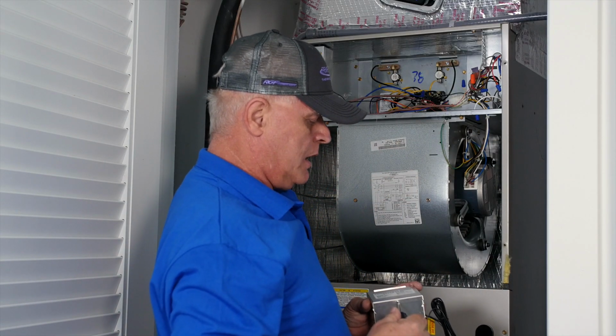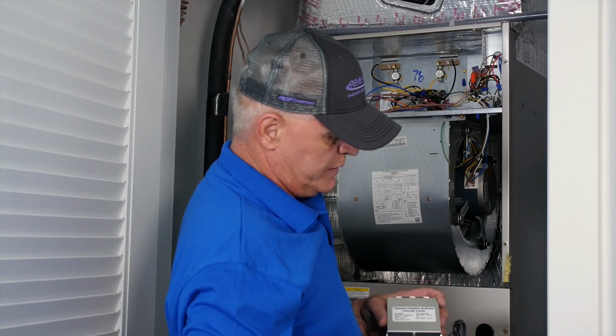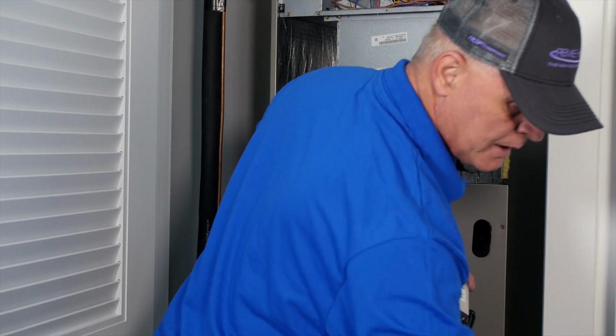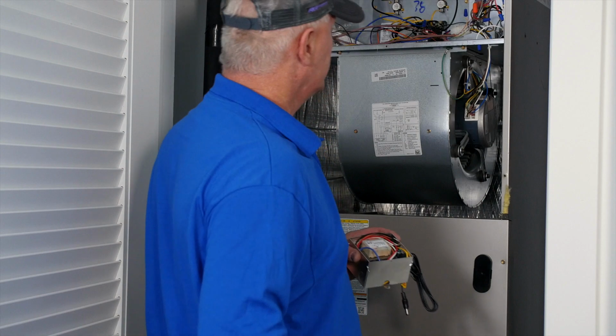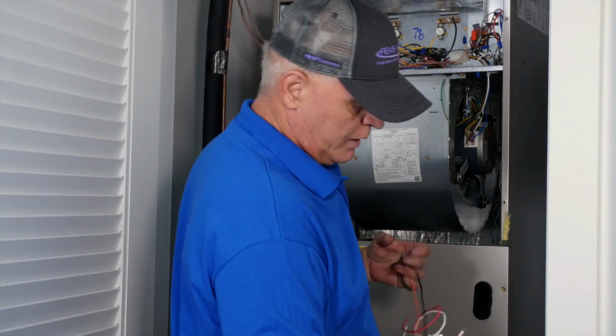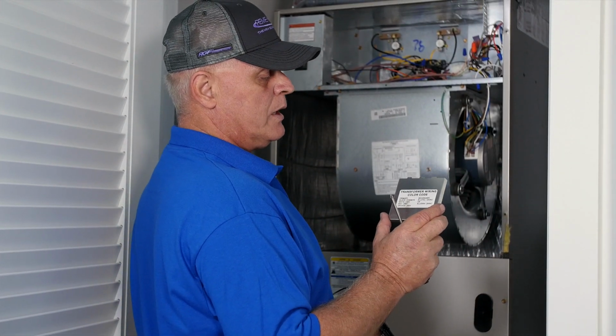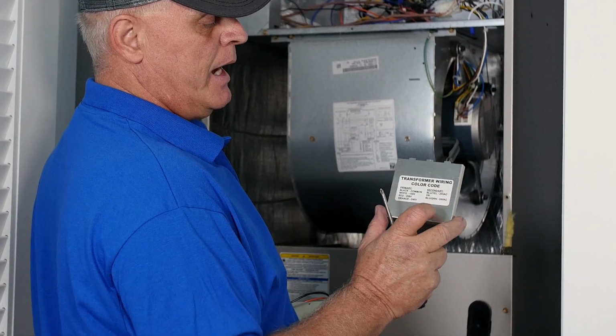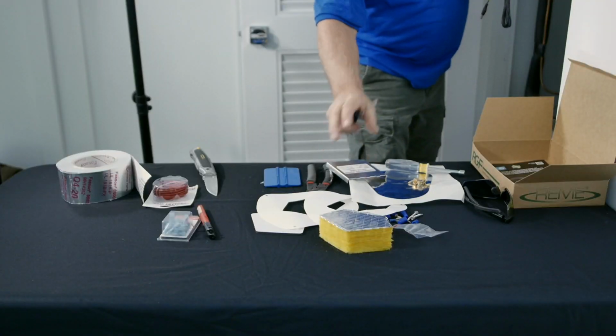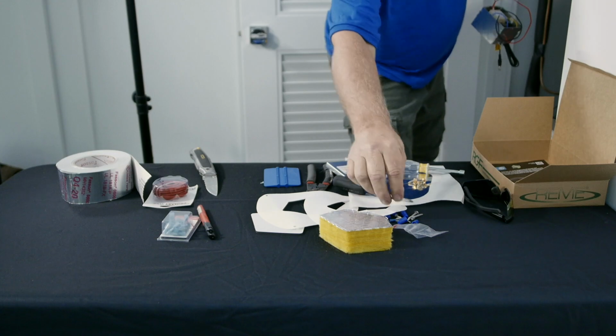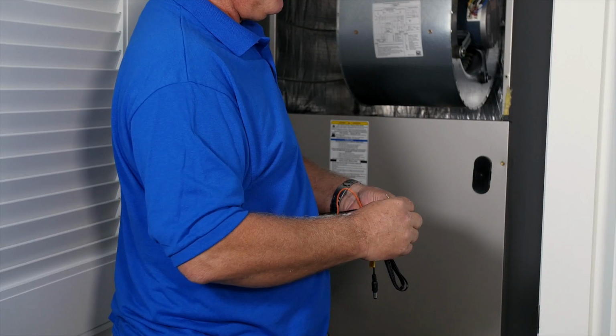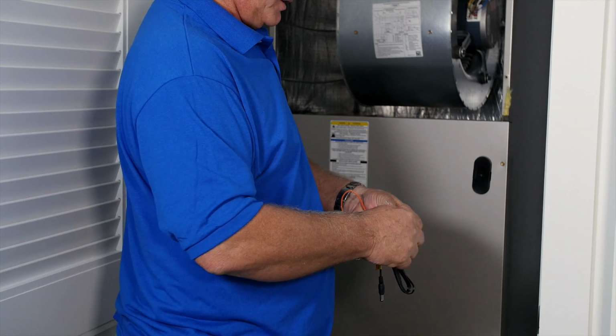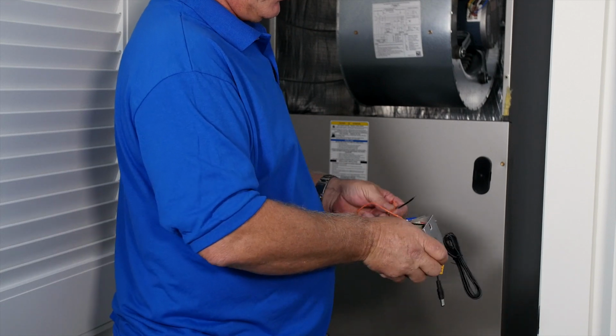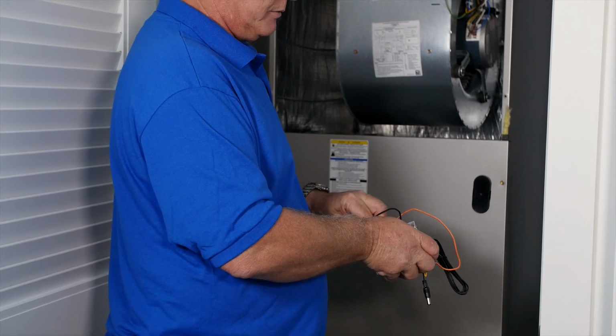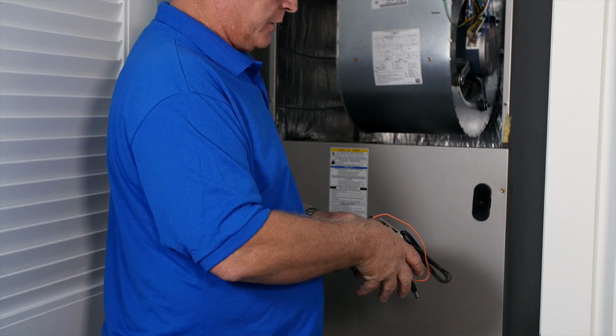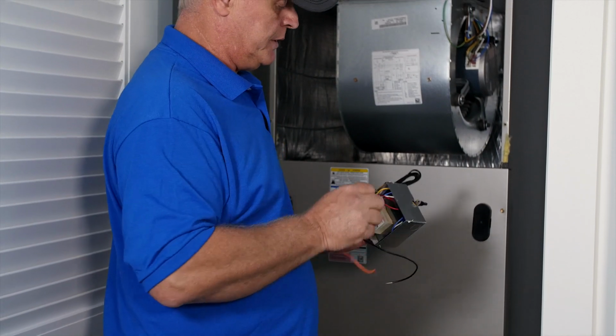The transformer has its wiring color code on the top of the box, so you need to understand which power you are going to be using. This particular unit is a 240 volt air conditioning unit, so according to our transformer color code, we are going to be using the black as the common wire, and as the 240 volt, the orange. The other 2 wires in here we are not going to be using. We need to isolate them. 240 volts needs to be your black wire and your orange wire, not your red. So these are going to be our line incoming, the black and the orange, for 240 volts. Alternatively, if you were using another voltage, you would be using the different types.